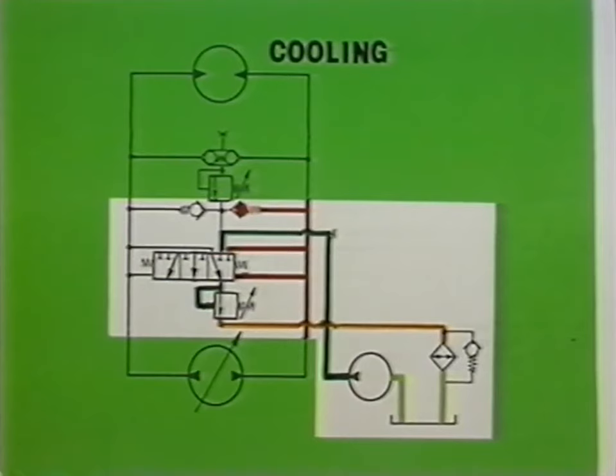High pressure now moves the shuttle valve to the left. The cooler inflow of oil is now fed through the left check valve and presses out the warmer oil to the cooler via the shuttle valve and the feed pressure relief valve to the tank.